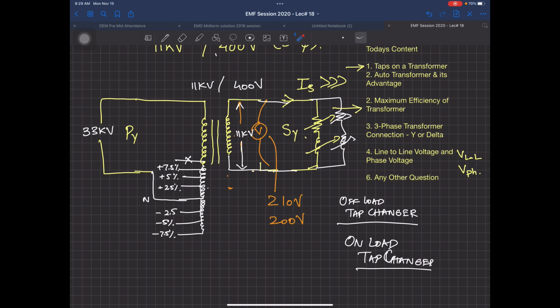There is always going to be some maintenance, so normally they schedule that maintenance after every season. Suppose in summer they connected this wire, but in winter when the load is less, the voltage will be higher. So they will bring the tap down to another point, connecting it there instead, since in winter you don't have much load attached — just like this room, where even now only one projector is working.